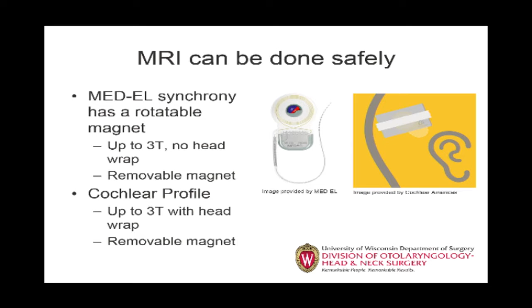The Cochlear Corporation's Profile device takes a slightly different strategy. Their magnet is removable. In other words, with a second smaller surgery, we can make an incision and take the magnet out if that is needed. Or they have a special little device that can be placed over where the magnet is, held in place with a head wrap to help hold the magnet in its correct orientation so that it doesn't shift with the MRI. And these, again, have been FDA approved up to 3 Tesla.